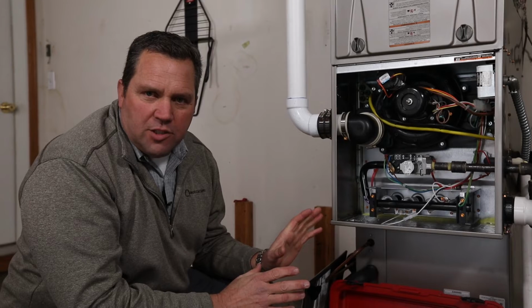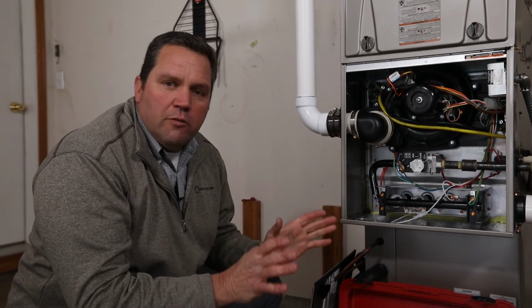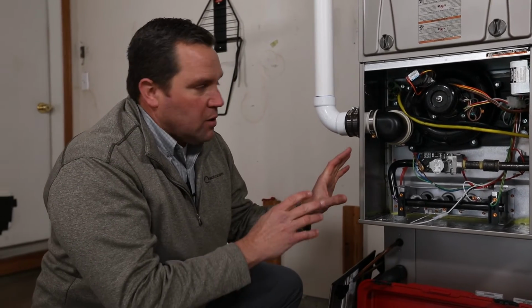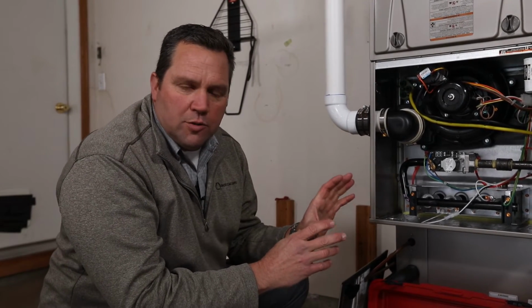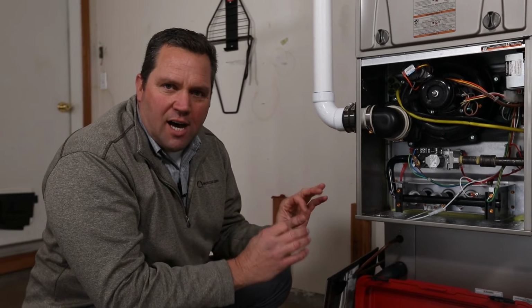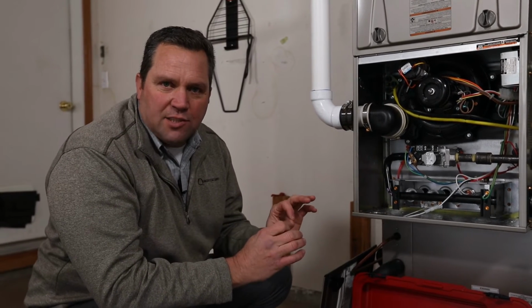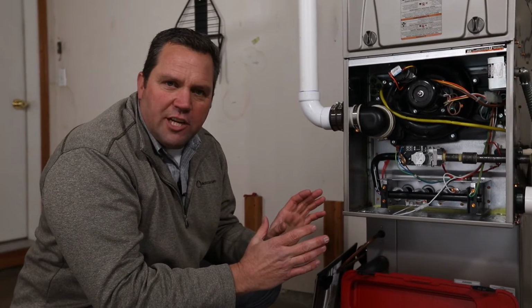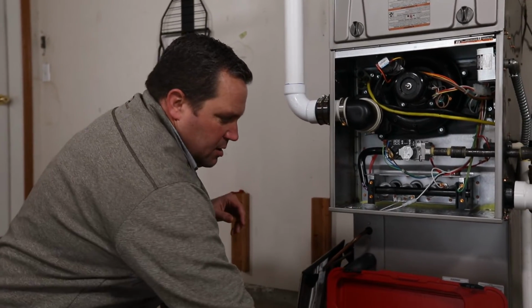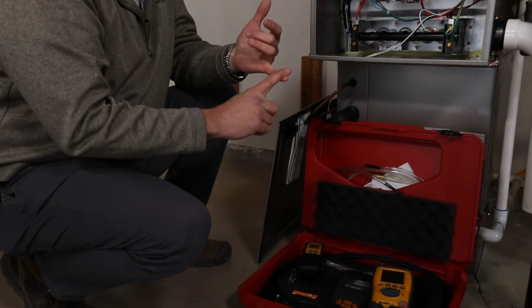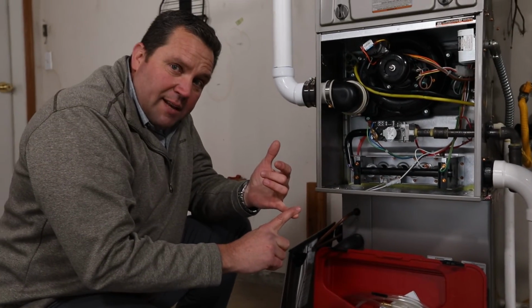When we look at the heat exchangers, there's a primary and a secondary, and we want to inspect both. What we're looking for is those pinholes or those cracks that could let hot, unburned gas release into the ductwork which goes into your system. We can check those heat exchangers by using a bore scope.